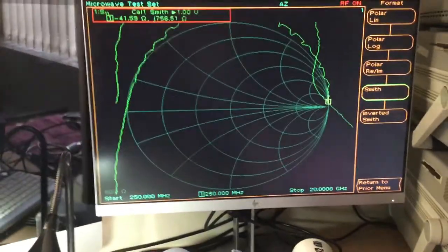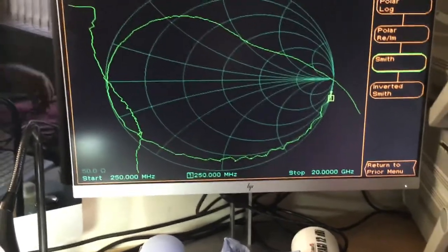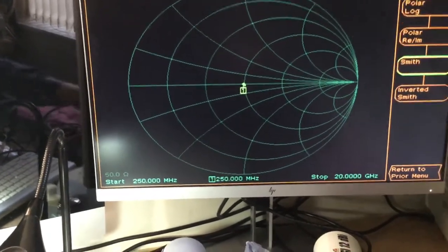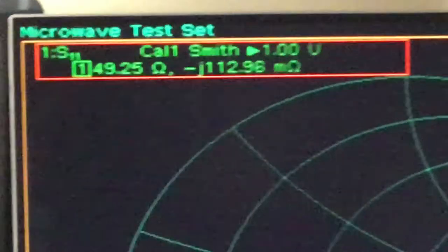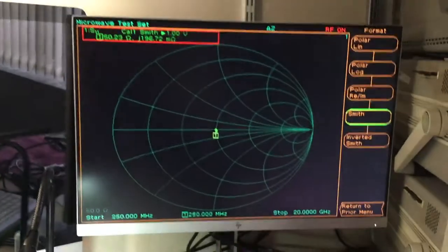So this is representing impedance, and at the moment if I connect a 50 ohm load onto the test port, which is a calibrated standard, this will then show us how accurate that 50 ohm load is. And as you can see there, if we zoom in slightly, in the top right hand corner it's telling us what the impedance is of that load, and it's bang on more or less 50 ohms.